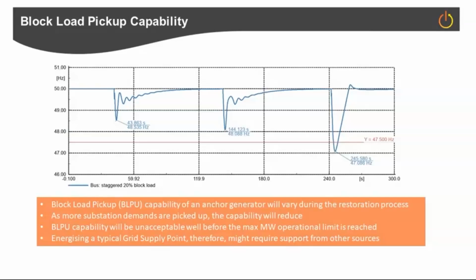And it does lend itself to the conclusion that in order to restore blocks of load further down into the restoration process, you need more assistance from other DERs within that geographical area, within that DRZ. So that's quite interesting. Just to give you some stats on that, a typical distributed energy resource that I'm talking about is a generator between about 20 and 50 megawatts. The block load capability for that kind of unit we found is roughly between about 10 and 25% of that generator's active power rating, which equates roughly to about 2 to 12.5 megawatts of block loads, depending on the kind of blocks.